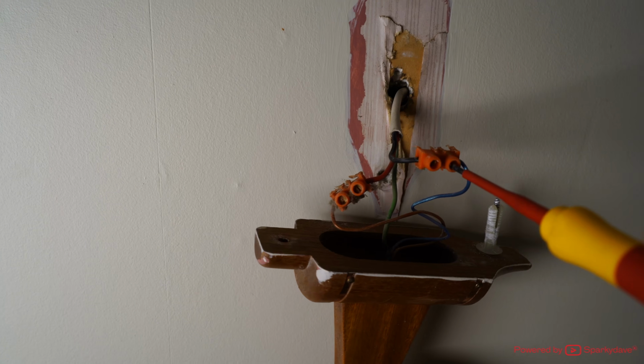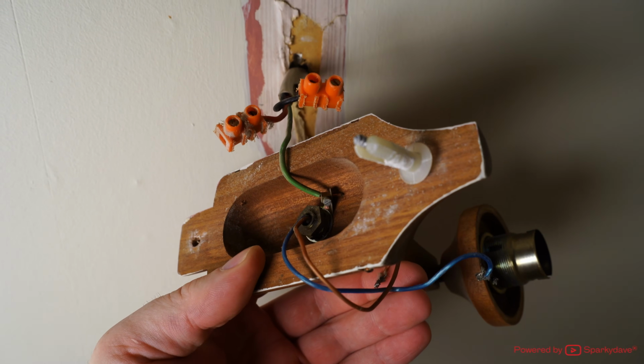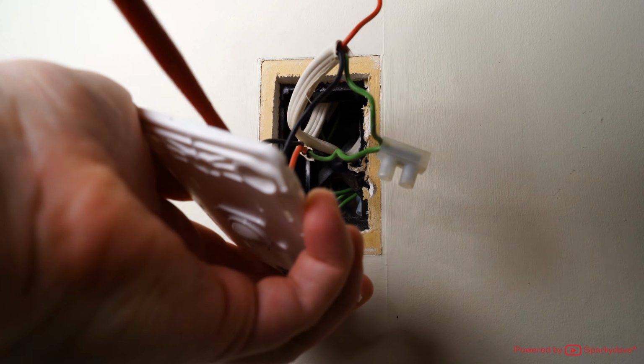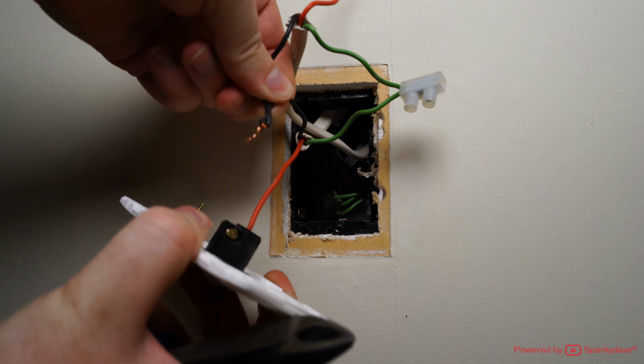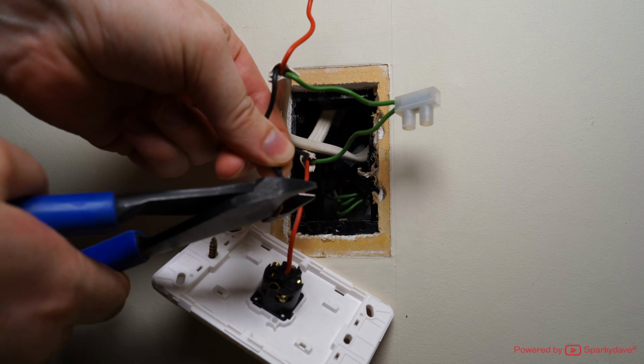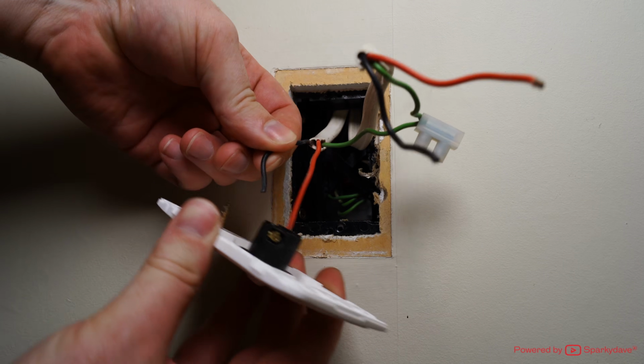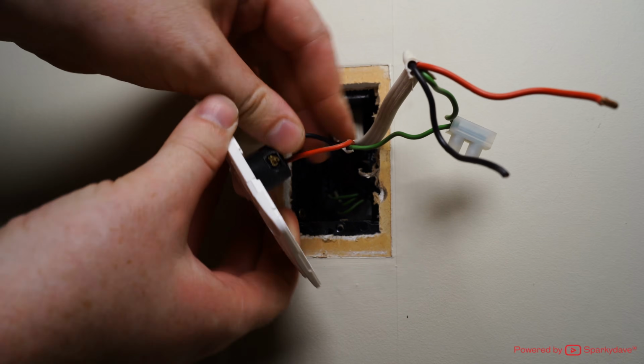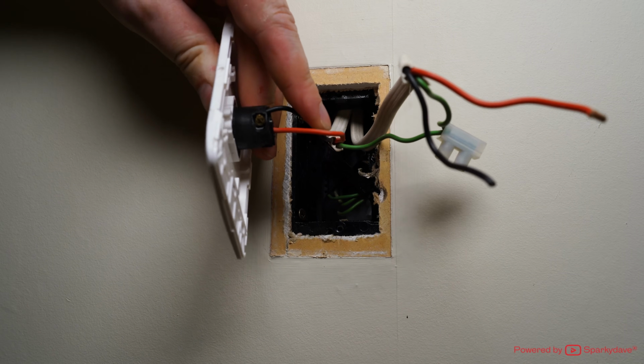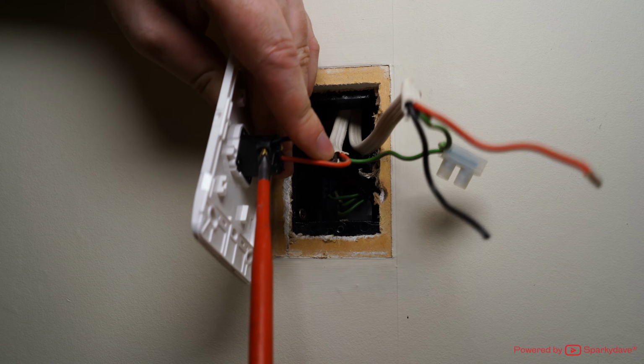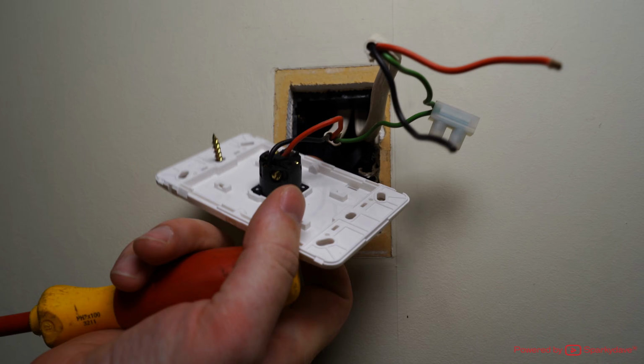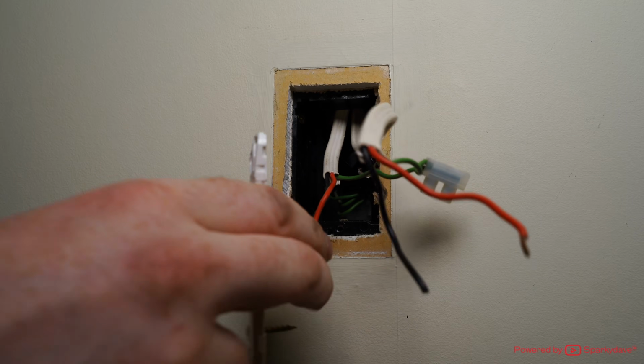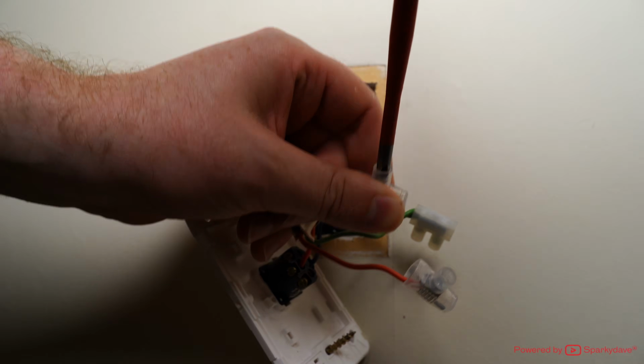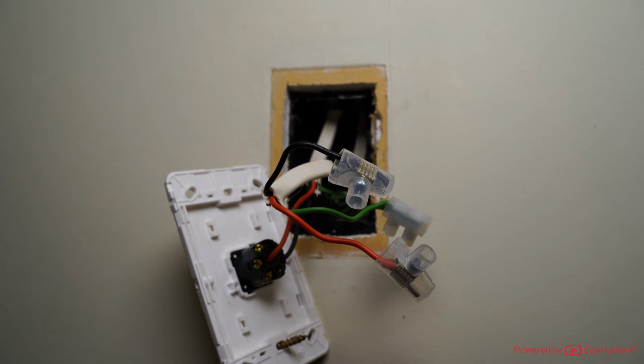Completely remove the wall light by disconnecting the cable ends, and disconnect the corresponding phase and neutral ends of the cable from behind the light switch. Leave the line side cables terminated into the switch. In this case, the removal of the light fitting is temporary and the light fitting will be reinstalled later. Where the light fitting requires permanent removal, ensure the cable is also removed from the wall. Install connectors onto the disconnected cable ends behind the switch and refit the switch plate back onto the wall.